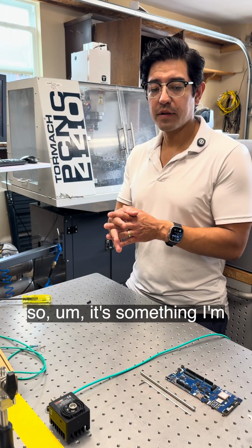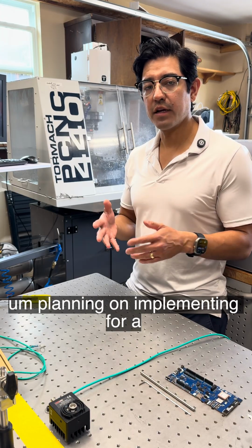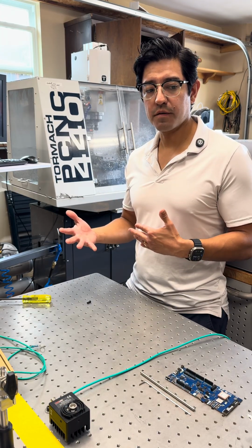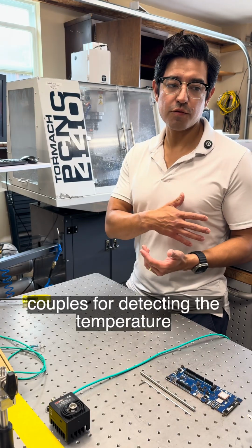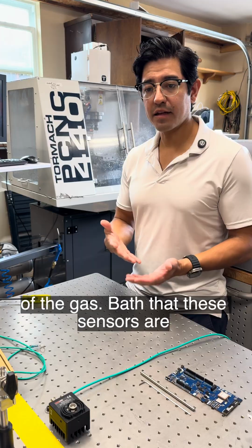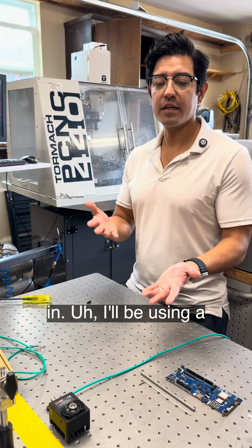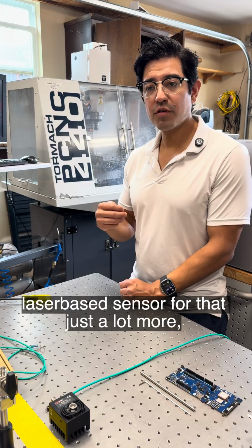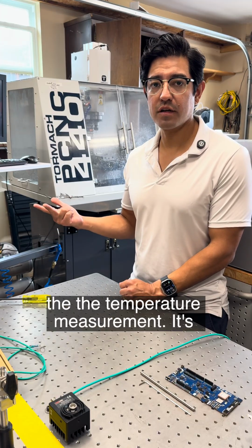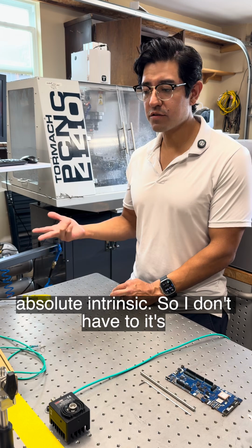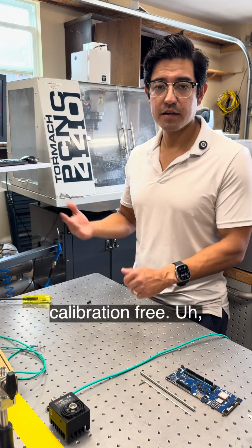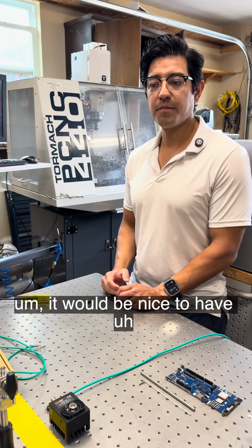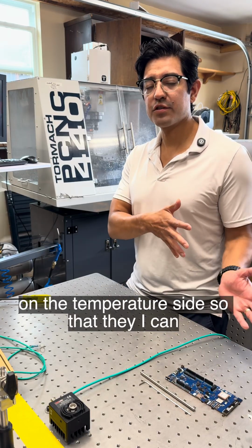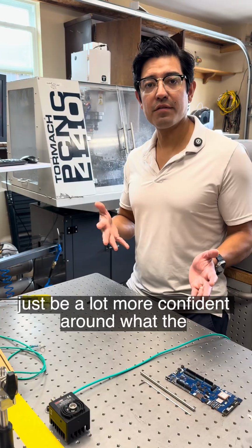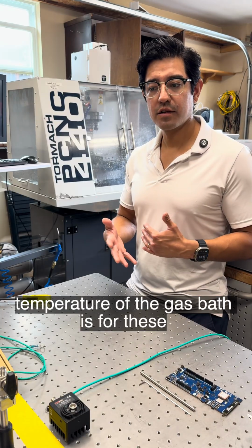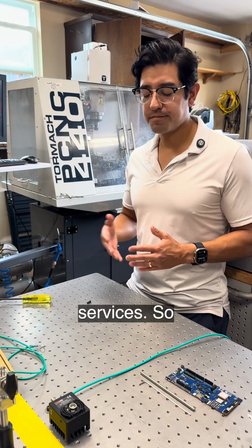And so it's something I'm planning on implementing for a calibration service where, instead of using thermocouples for detecting the temperature of the gas bath that these sensors are in, I'll be using a laser-based sensor for that. Just a lot more precision, accuracy, and control over the temperature measurement. It's absolute, intrinsic, so it's calibration free effectively. And so it'd be nice to have on the temperature side so that I can be a lot more confident around what the temperature of the gas bath is for these calibration services.